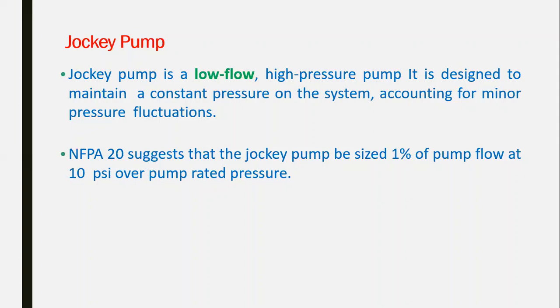running, and the pressure will go higher. It has to be discharged from the pressure relief valves, or it has to be released from the circulating relief valve if it is electrical, etc. And it cannot be stopped unless it is manually released and shut off. This affects the operation of the fire pump itself, which is required for life safety and is very expensive equipment. So we have to avoid operation of the fire pump, which we call malfunction, maloperation or false alarm from the fire pumps, and keep the fire pump ready to work exactly in the case of fire. That's why we have the jockey pump here.